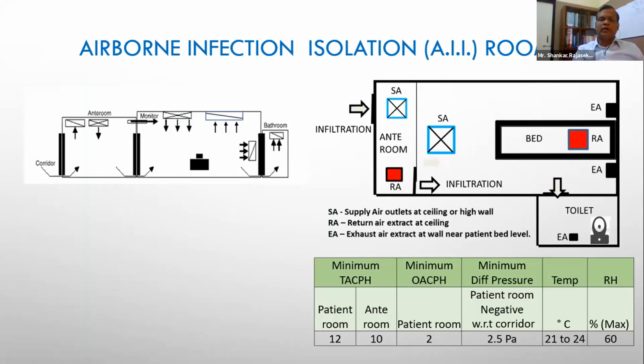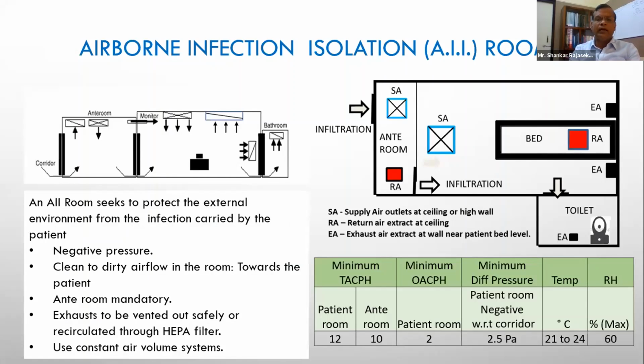Since it is isolation, I thought I would give some values because it might be important these days. How many air changes are required? And in a negative pressure isolation room, an anteroom is mandatory. We have to have a separate anteroom. It's characterized by negative pressure and clean to dirty airflow direction. Exhausts are to be vented out safely at a suitable height, or they can be recirculated back through HEPA filters. It's very clear. You can't recirculate the air from an AII room back into the air conditioning system without the use of HEPA filters. And it uses constant air volume systems.